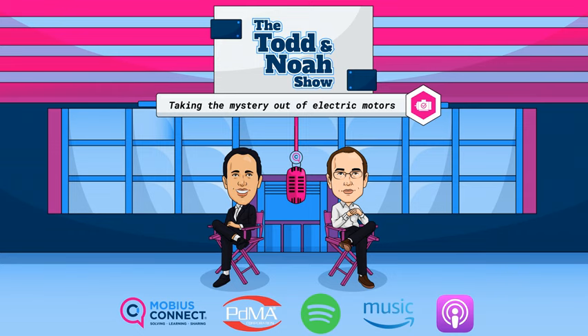So tell me what kind of data we should be collecting to analyze if we have power quality issues. What are we looking for? That's a good question. One of the things, because you always hear about harmonics, right? That's something we don't want to miss. But for the most part, we look at the voltage quality, voltage imbalances and stuff, which kind of lean a little bit more towards the power circuit fault zone. But we certainly want to pay attention to that as well. But we're going to source from the voltage and the current distortion levels, and you'll hear us talk about harmonic voltage factors and derating factors, things that are going to be affected by these harmonics. And of course, not just total harmonic distortion, but the total harmonic distortion of current, right, which is a little bit different. And we'll talk about how an individual leg in a power system may have different harmonics than the bus itself. But certainly we'll probably focus a lot on the distortion and the different levels of harmonics.